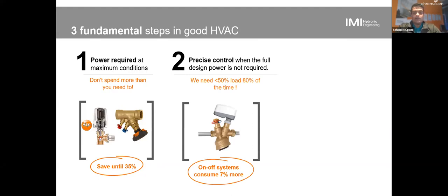Similarly, when we start getting into partial load, we want to make sure we have good control in the system as well. We operate at less than 50% load for 80% of the time, and that's responsible for a large amount of energy consumption. So we want to have proper control valves selected, proper control mode selected. Just using on-off versus proportional can consume 7% more energy overall in your HVAC installation.